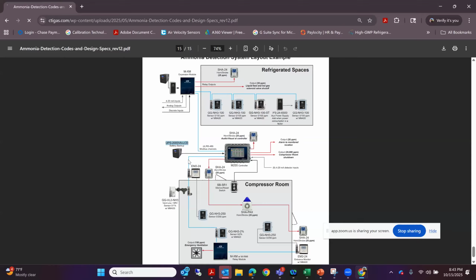Well, you don't want to try to run 350 milliamp off each sensor when you could be running 40 or 100 during an event where you don't have power. I know that's some of the things that have been talked about on the gas detection side on our end, to really help get as much time and less drain on that dedicated branch circuit or UPS rack mounted system that a person might go with.